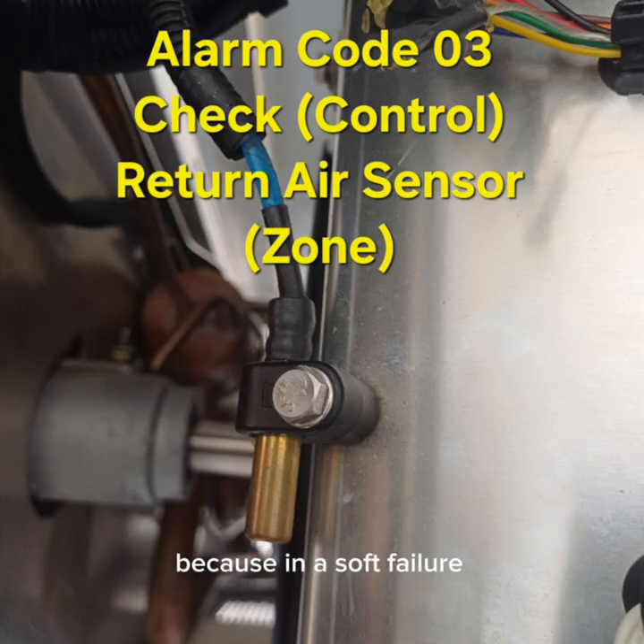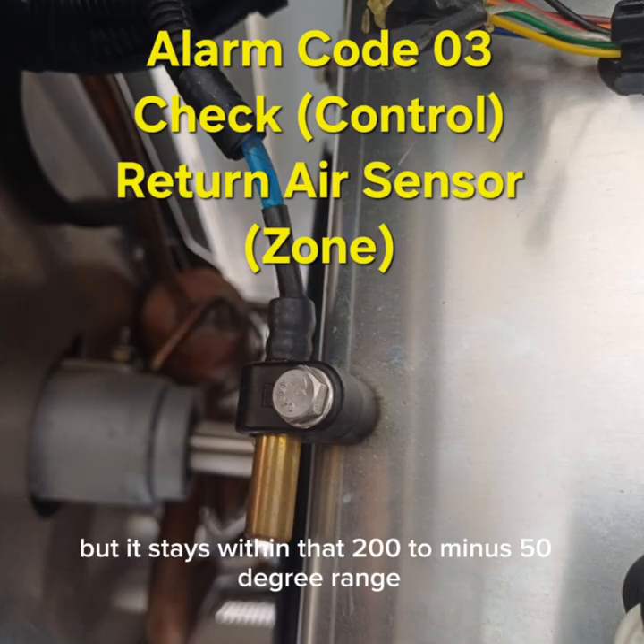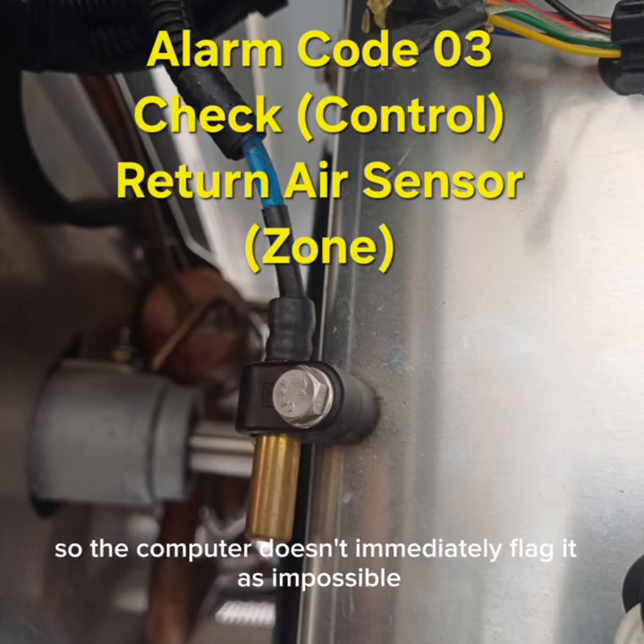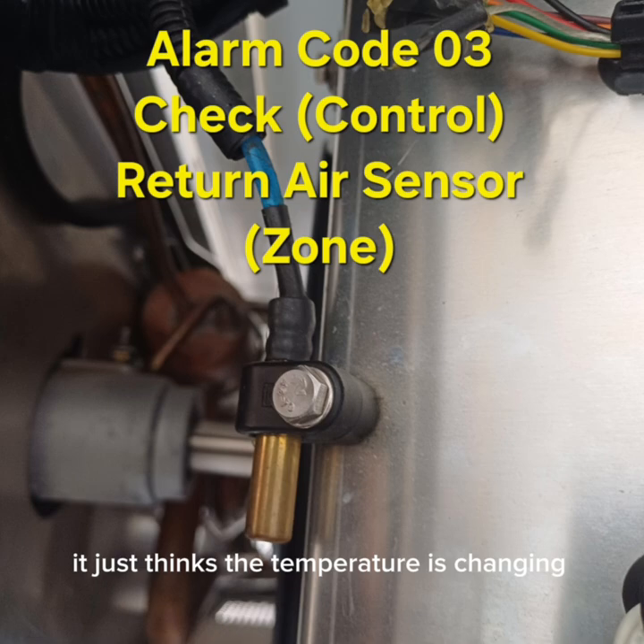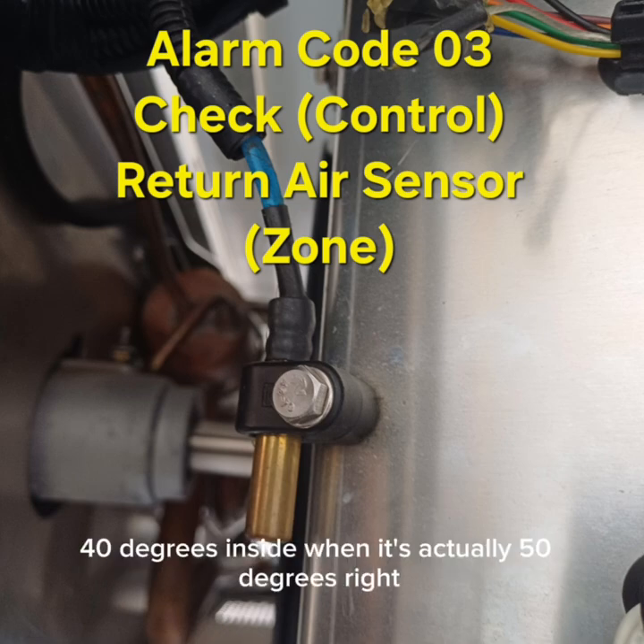Why? Because in a soft failure, the sensor's still talking, it's just lying. And it's a believable lie. Oh, that's much worse. Much worse. In a soft failure, the reading is erratic or it drifts, but it stays within that 200 to -50 degree range. So the computer doesn't immediately flag it as impossible, it just thinks the temperature's changing. So the unit might think it's, say, 40 degrees inside when it's actually 50 degrees.